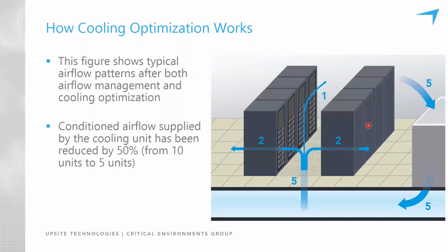So sealing the raised floor was a very good thing. It created the opportunity now to reduce the amount of air flowing through the room and balance the ratio of conditioned air to IT demand air. The IT equipment needs a total of 4 units of air.